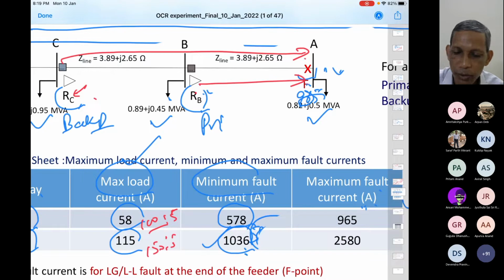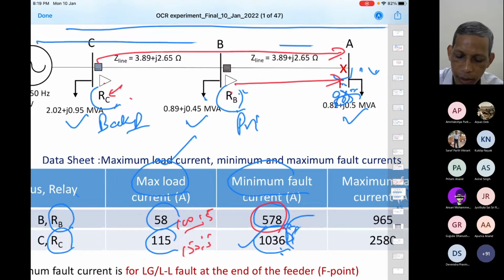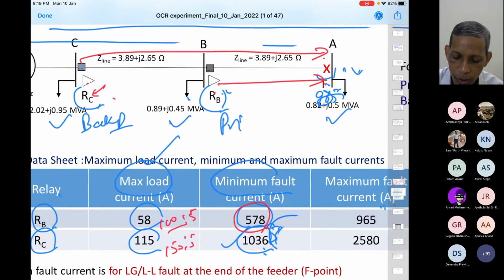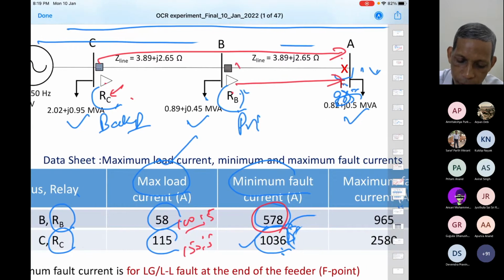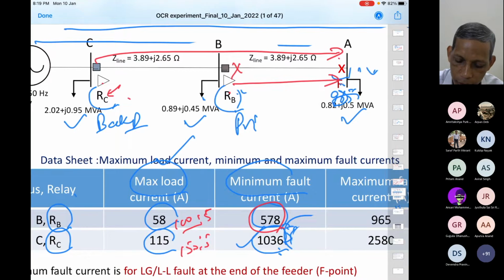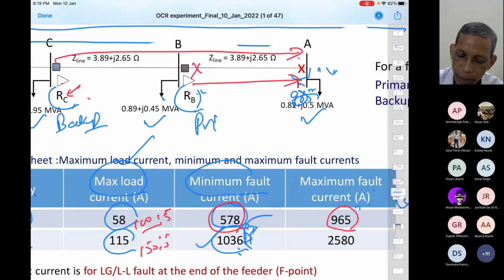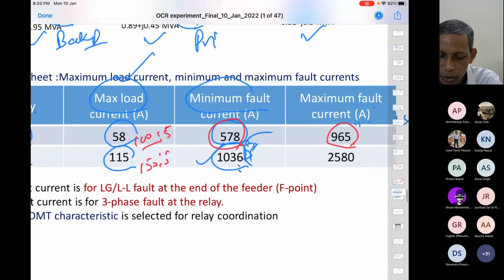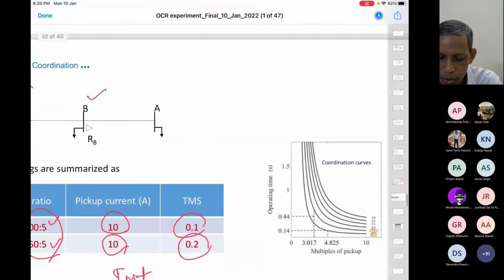So the minimum fault current which RC should take care of is again this 578. 578 for both RB and RC. And the coordination is between what? The fault which you create here, the three-phase fault here, is the maximum fault current seen by RB, and that is nothing but 965. At 965 ampere, you coordinate between this and this, and at that time you keep the corresponding curve of RC higher than this one. So this is what you do for this perspective.